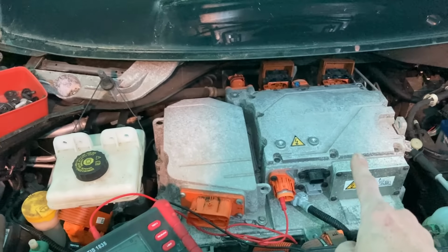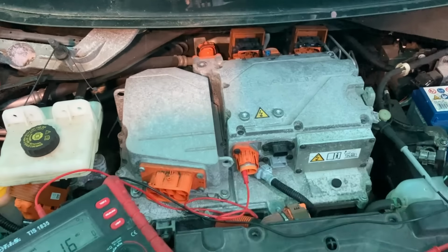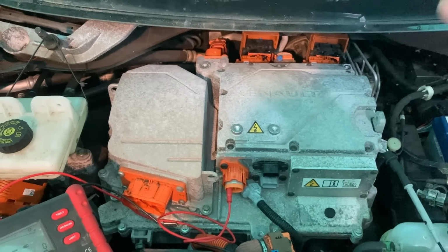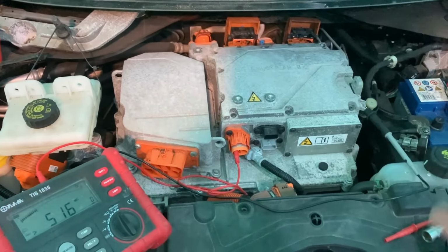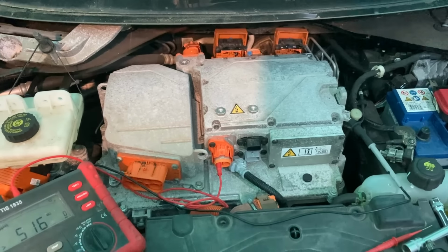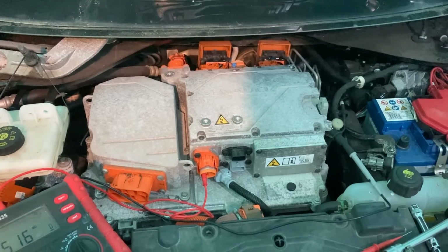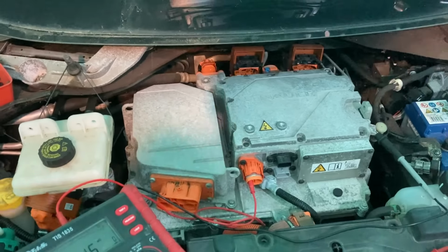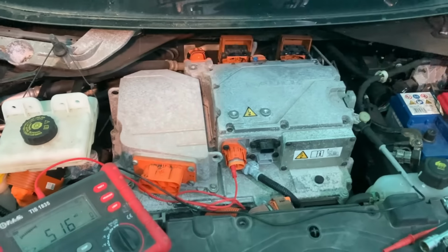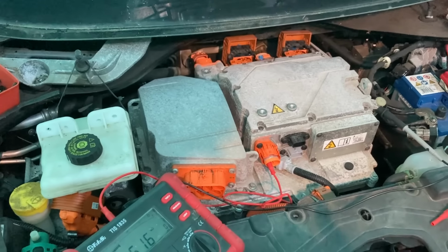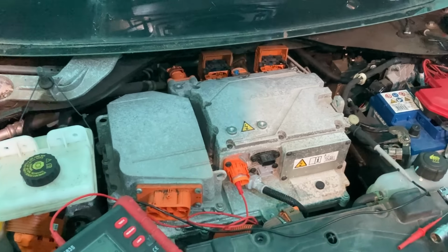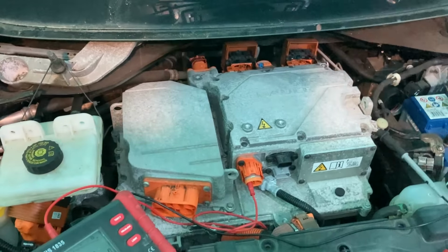So then I'll potentially remove this box as a next step, and then we can investigate further down. The motor and the motor controller are still connected together, so we could potentially have a fault in, say, the motor, but that represents as a fault through the motor controller, because the motor's just a dumb component connected to the controller - or an issue just in the controller. So we need to go to the next stage.